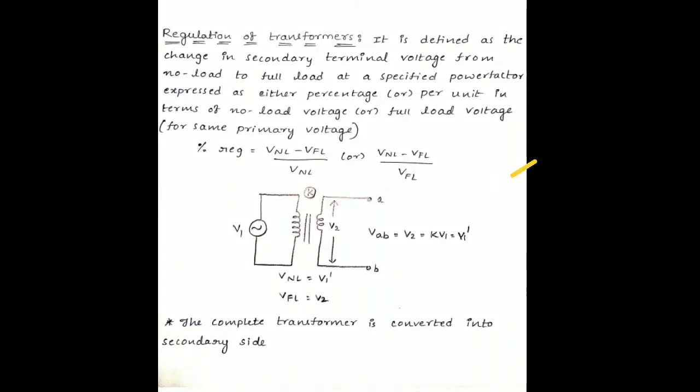Hi everyone, good morning. Today I would like to discuss the regulation of a transformer. Before going to that, let us define what regulation is. Regulation is defined as the change in secondary terminal voltage from no load to full load at a specified power factor. That is, the power factor of the transformer should be maintained constant, and it is expressed either as a percentage or per unit in terms of no load voltage or full load voltage.